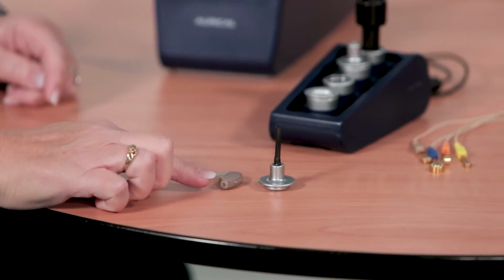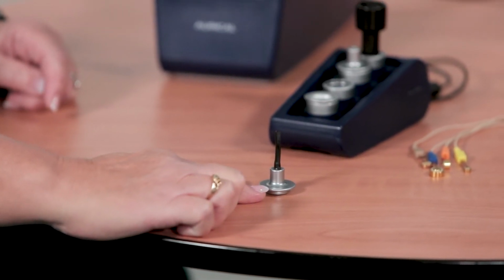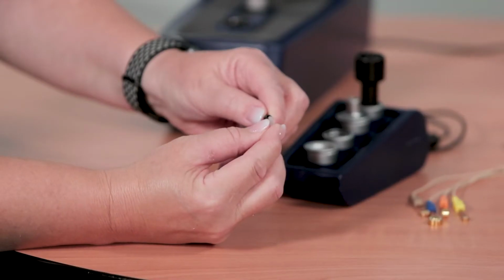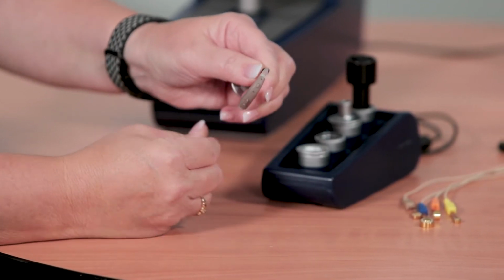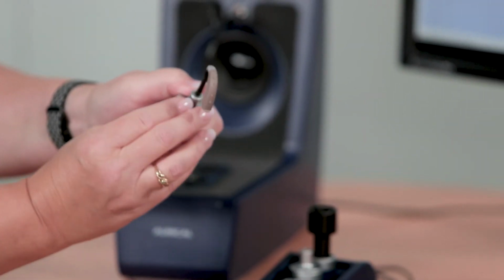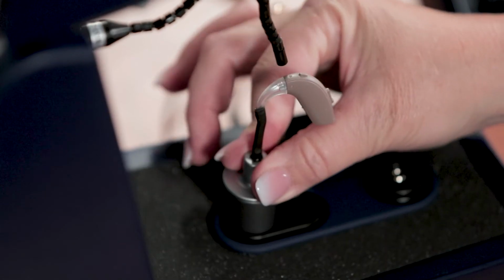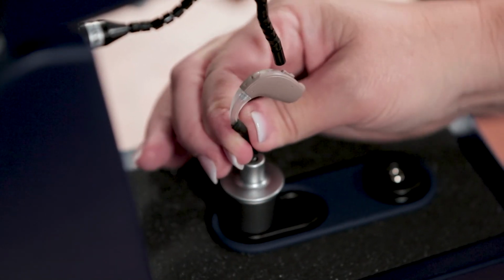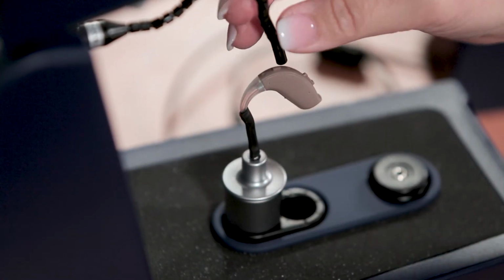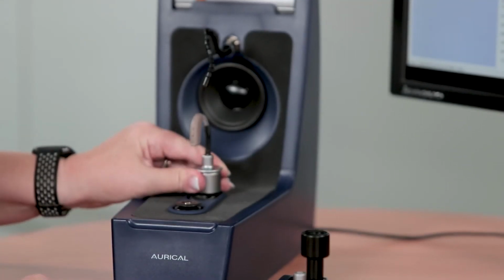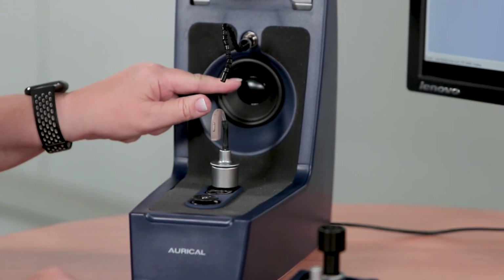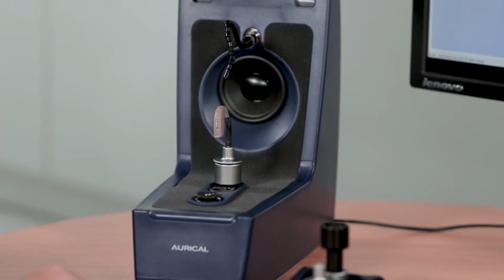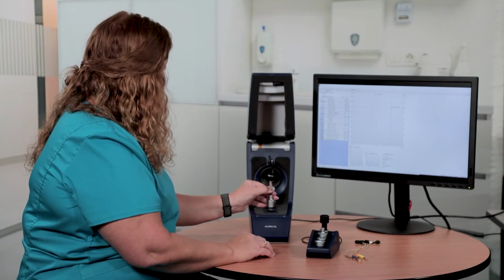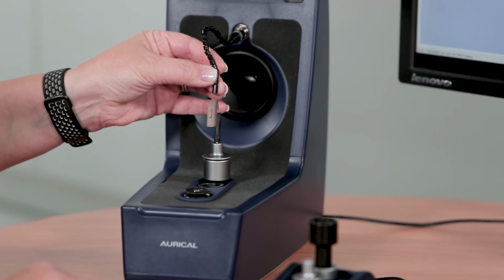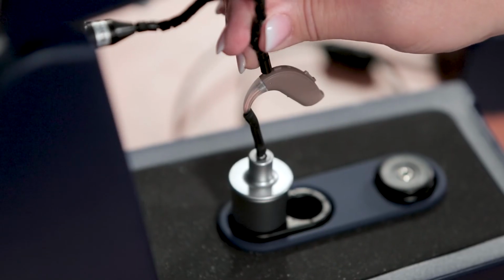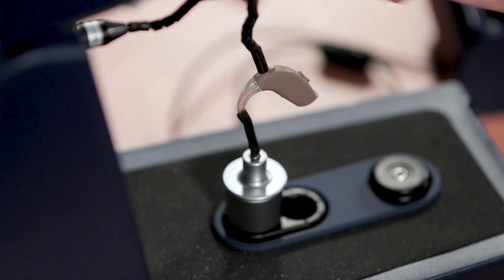For BTE devices, the HA2 adapter will be used. Simply connect the hearing aid to the provided BTE tubing, and then connect this to the HA2 adapter. Snap the HA2 adapter into place on the coupler, and insert the coupler microphone into the microphone port closest to the Aurical HIT speaker, the lower microphone port, so the hearing aid position is level with the middle of the Aurical HIT speaker. Position the hearing aid with the front-facing microphone toward the Aurical HIT speaker, and the reference microphone as close as possible to the front-facing microphone on the hearing aid without touching it.